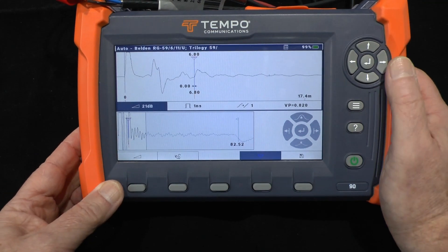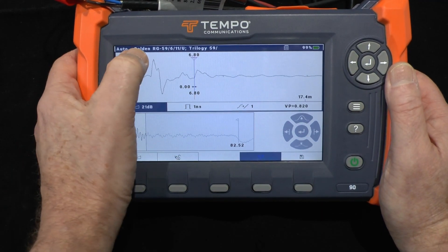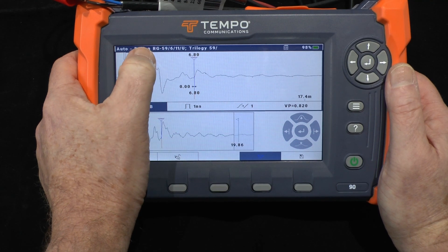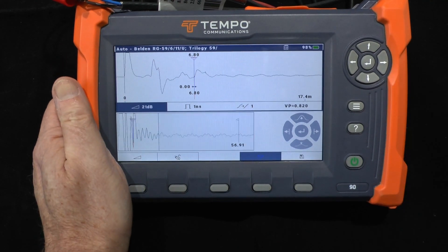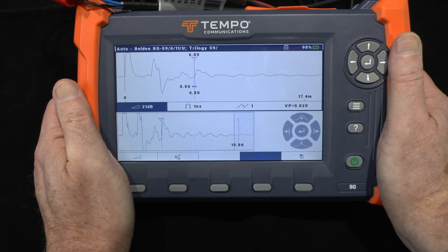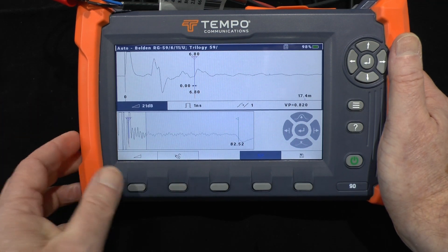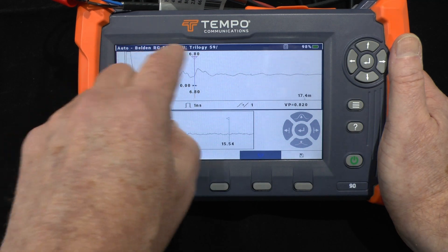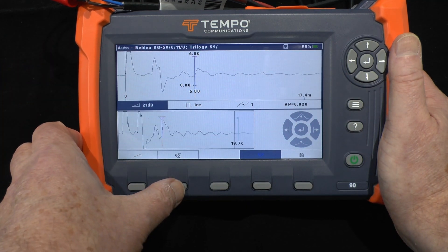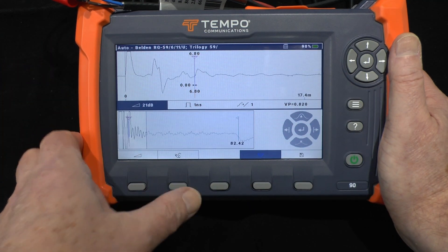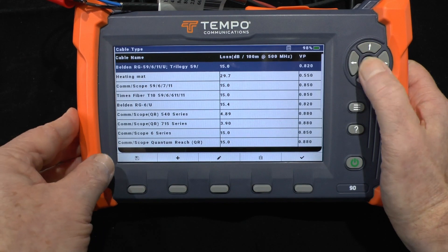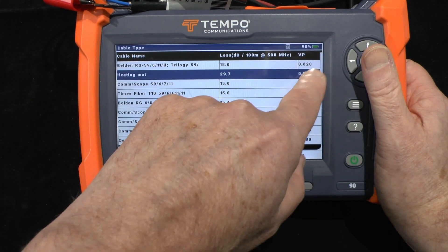That reading is actually incorrect because at the moment I've got an automatic cable type selected as a coaxial cable. It's important to know the characteristics of your cable beforehand — this is definitely not an RG59 coaxial cable. In this case I have it set up as a custom heating mat cable with a VP of about 0.55.